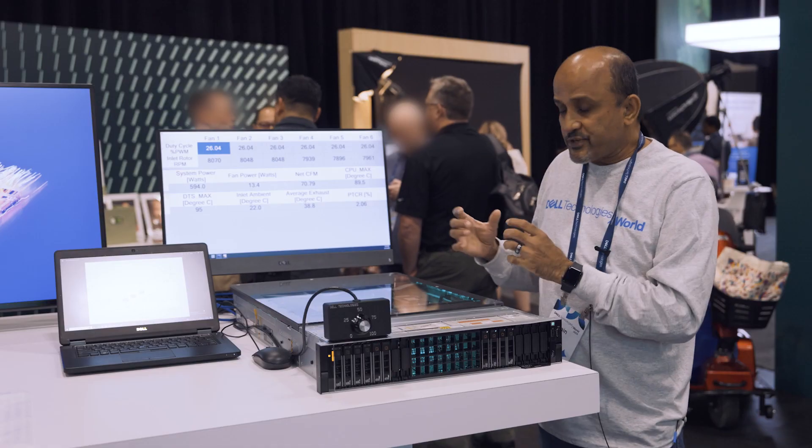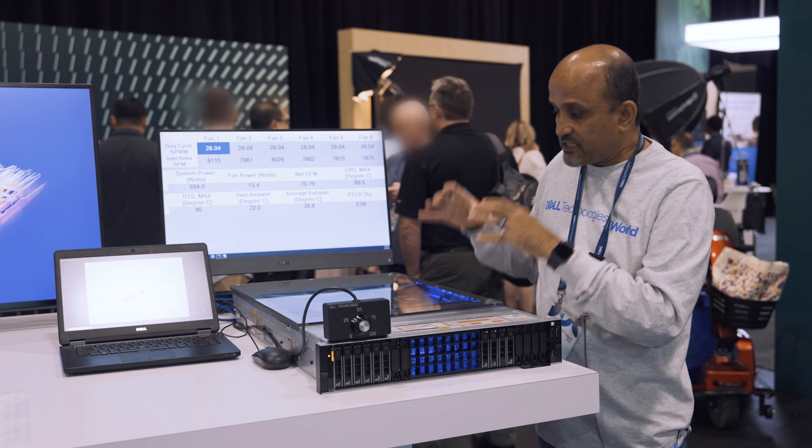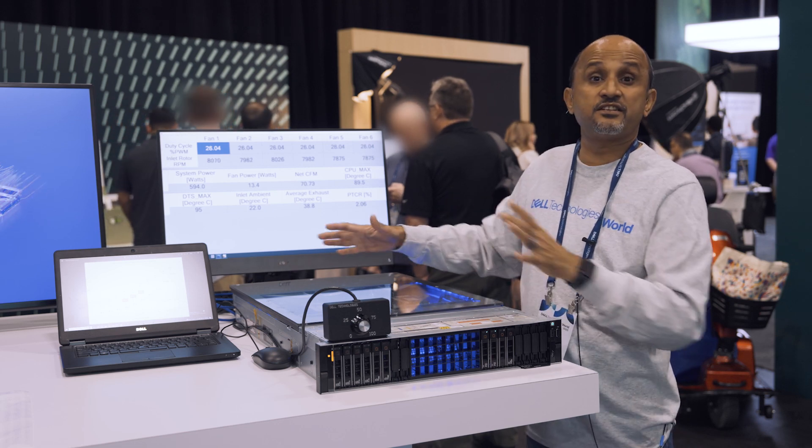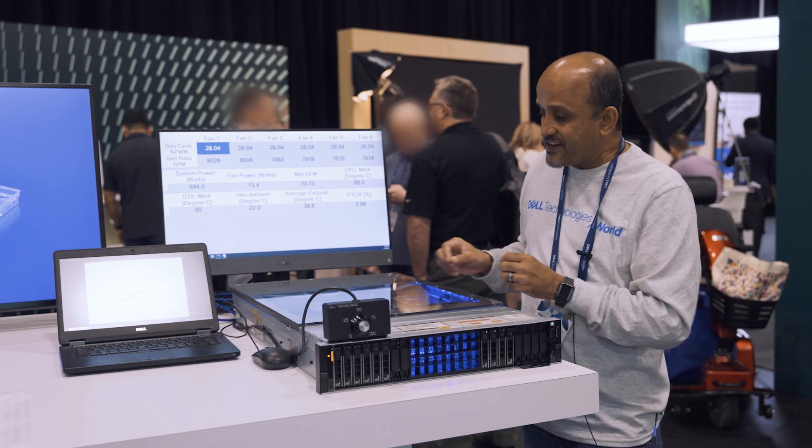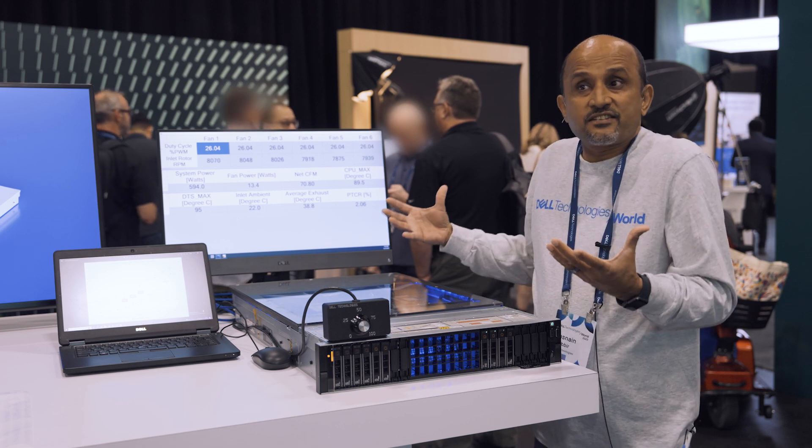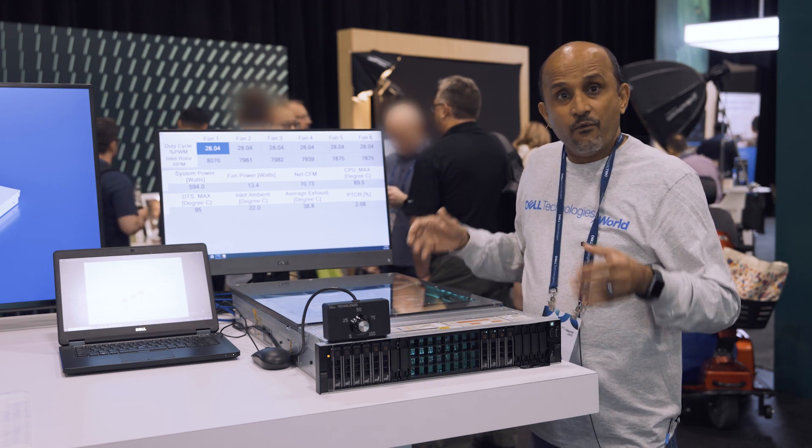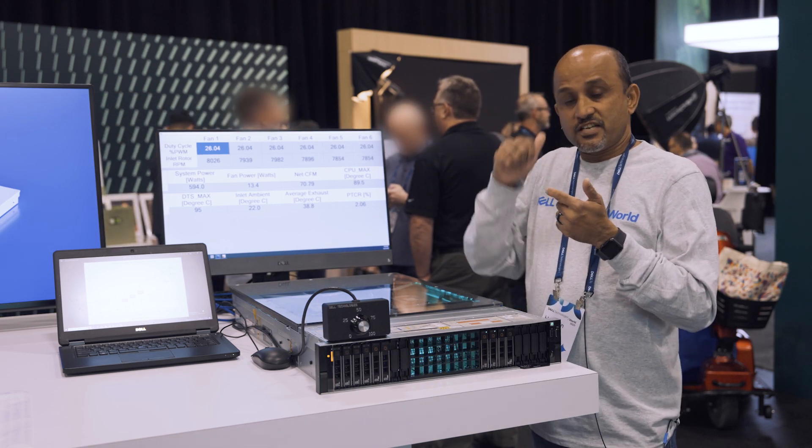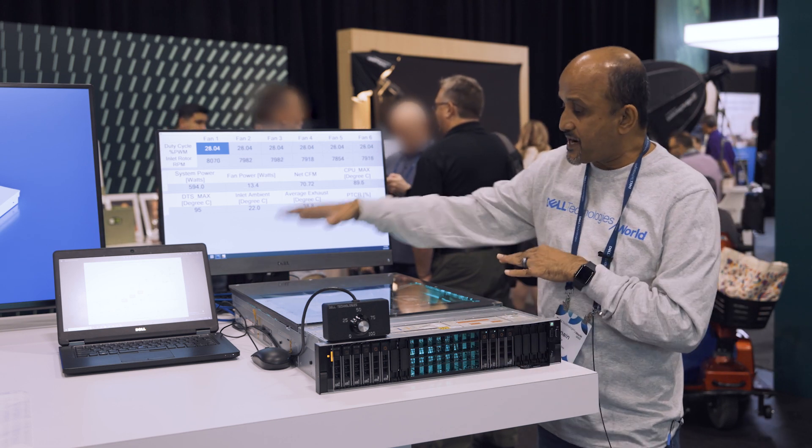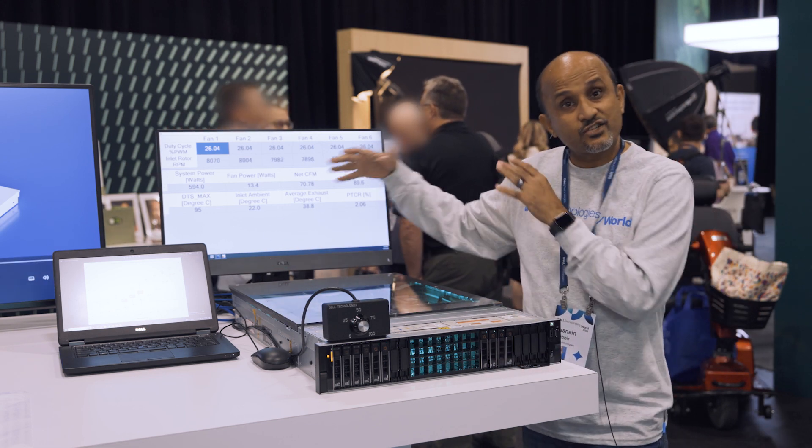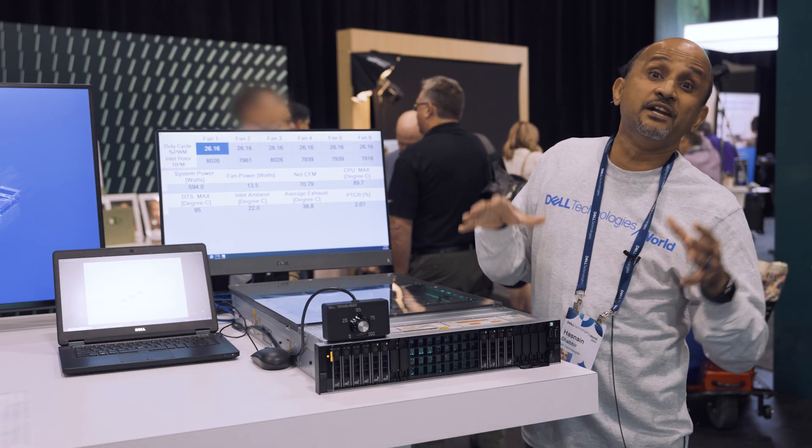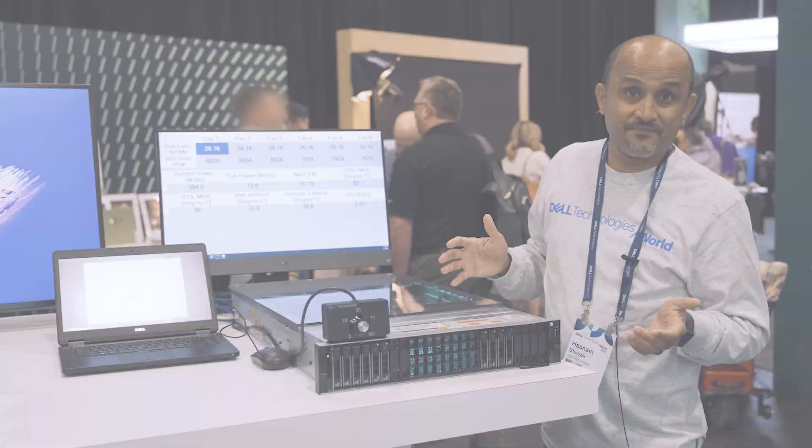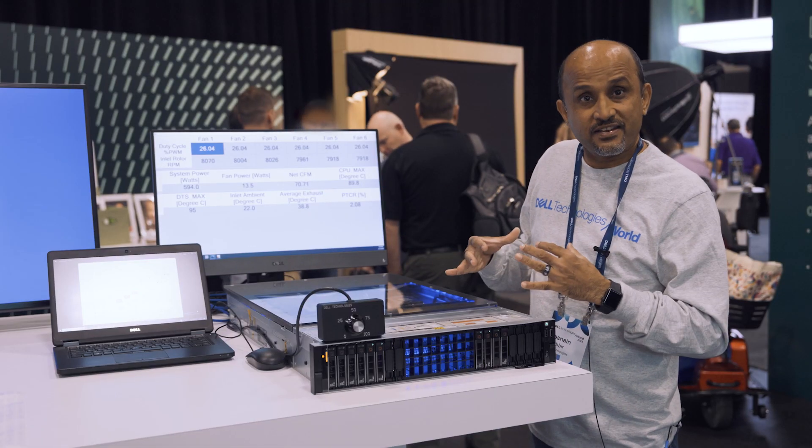This helps you fine-tune the fan speed as a function of sensors in the box. Our systems contain 50 to 70 sensors for a specific config, which means we are monitoring CPU temperature, memory temperature, drive temperature, PSU temperature, exhaust temperature. We are dialing the fan speed so that all of these work in unison to the lowest possible fan power state without sacrificing cooling or reliability of the box.